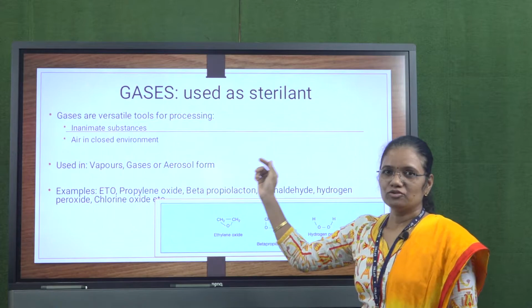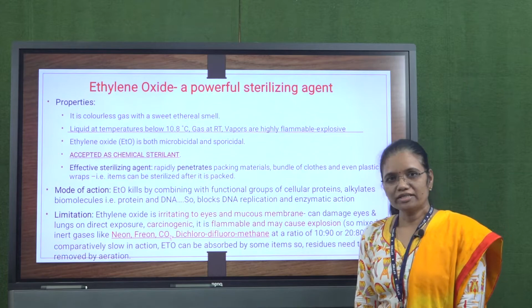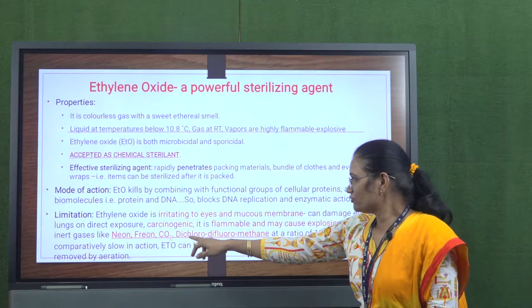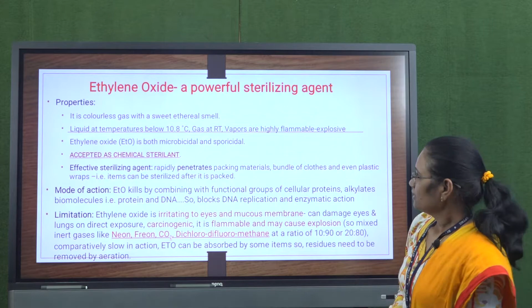Ethylene oxide is an excellent sterilizing agent with respect to its capacity to kill vegetative cells as well as spores, and so it has been accepted as a chemical sterilant. However, there are some limitations. Ethylene oxide is found to be explosive or inflammable in certain cases when its concentration rises. So, looking at its limitations of flammability and explosiveness, it has been mixed with inert diluent gases like neon, freon, carbon dioxide, etc. to prevent these accidents.